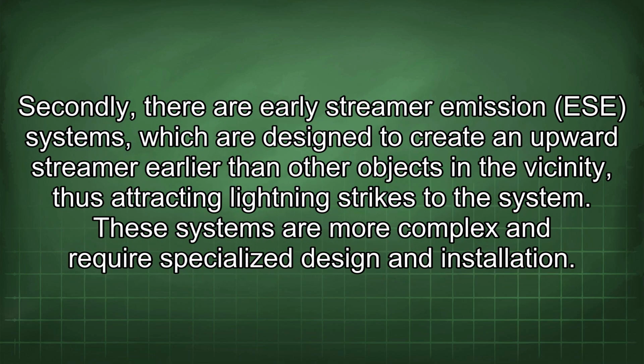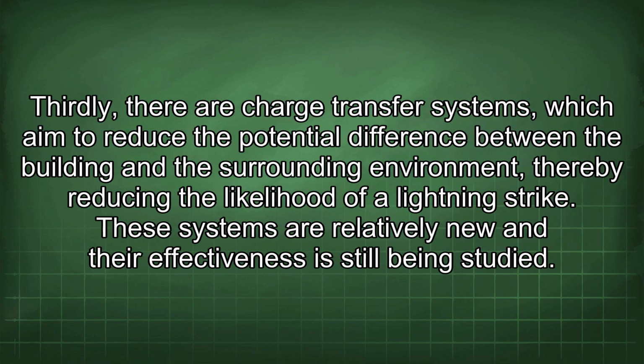Secondly, there are early streamer emission (ESE) systems, which are designed to create an upward streamer earlier than other objects in the vicinity, thus attracting lightning strikes to the system. These systems are more complex and require specialized design and installation. Thirdly, there are charge transfer systems, which aim to reduce the potential difference between the building and the surrounding environment, thereby reducing the likelihood of a lightning strike. These systems are relatively new, and their effectiveness is still being studied.